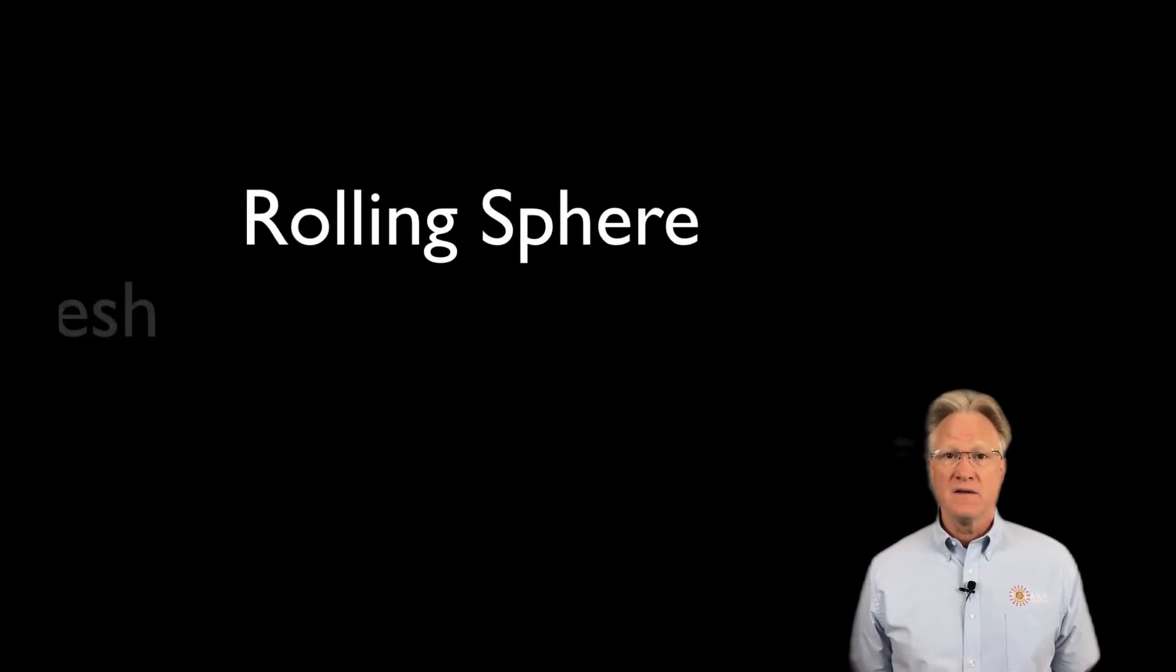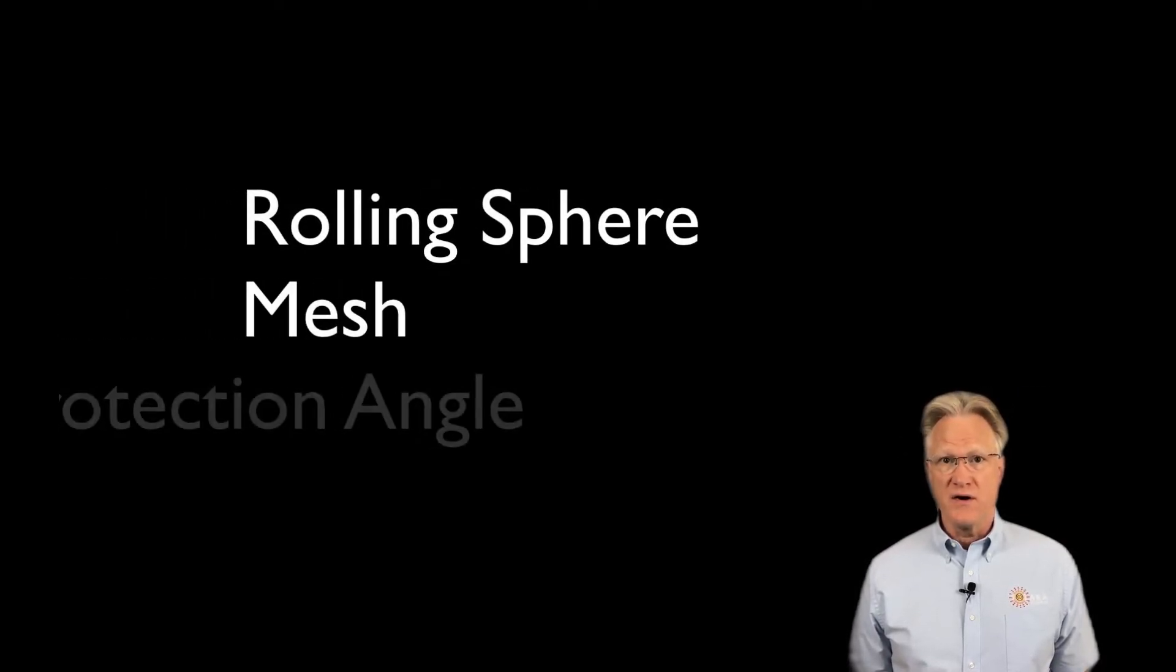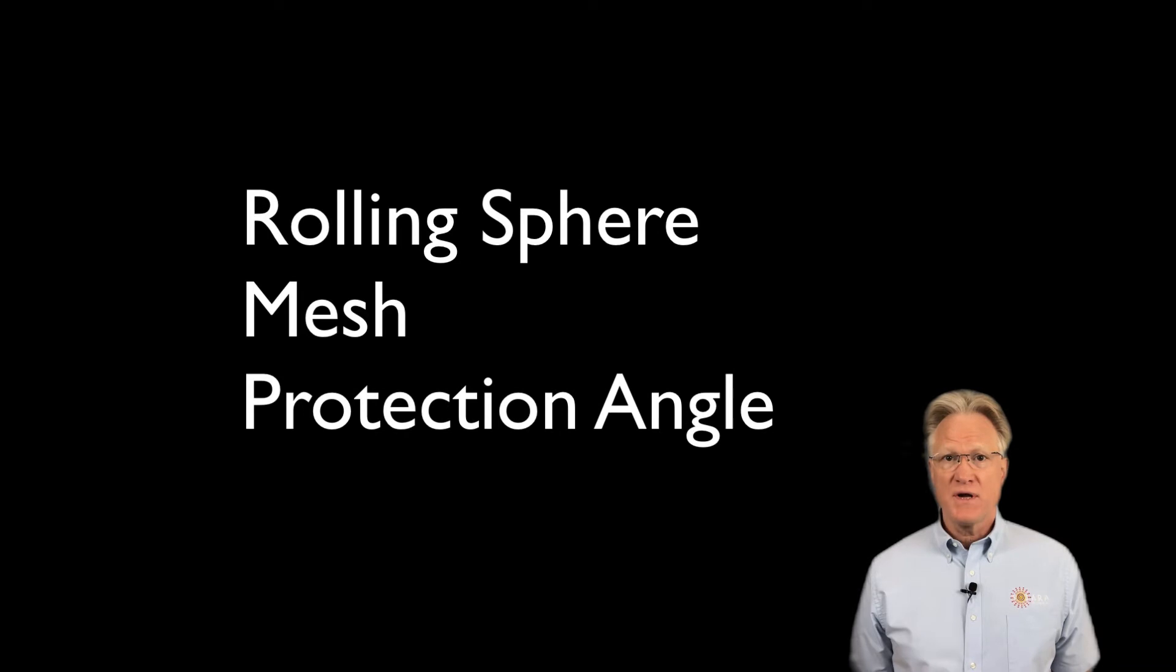Today I'll discuss how grounds are used to protect buildings from lightning strikes. There are three main methods used to design lightning protection systems: the rolling sphere, mesh, and protection angle methods. All get you to the same place with different equations.